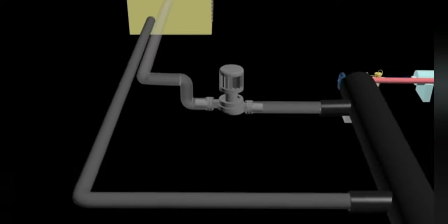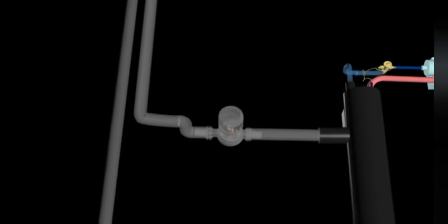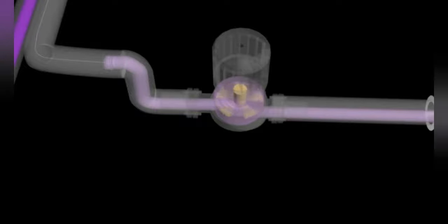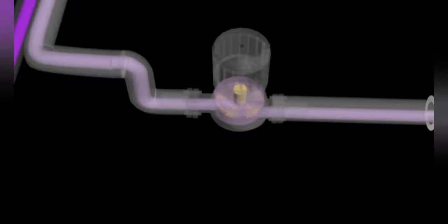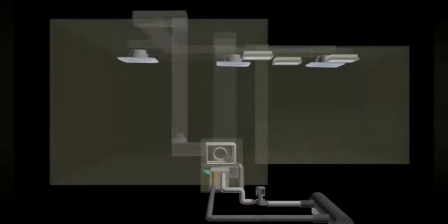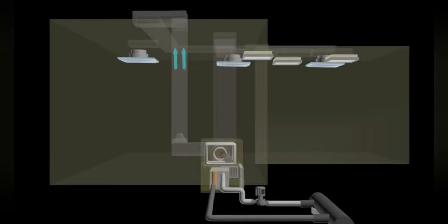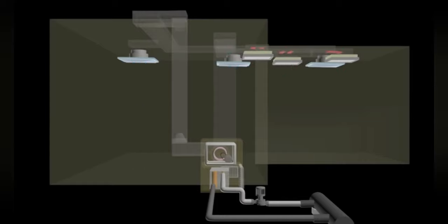This cycle continues as long as the pump is functioning. The pump used is the centrifugal type, which works based on centrifugal force produced by a rotating impeller in the pump casing. For air flow, an auxiliary centrifugal fan creates an air cycle drawing air from the room, mixing it with fresh outside air, delivering it to the air handling unit and back to the room. The fan is powered by a motor connected through belting.